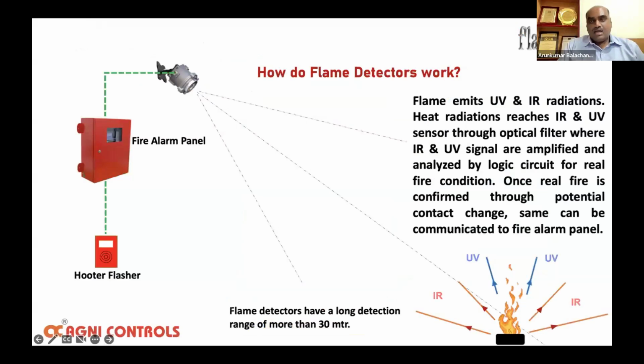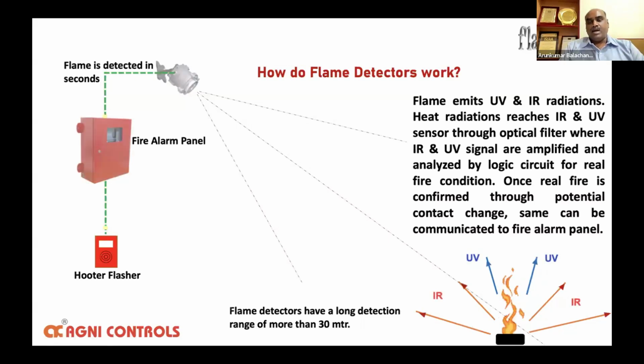So I had compared the flame detectors to our eye. How does the flame detector work? The flame detector picks up the invisible ultraviolet and invisible infrared radiation from a flame. When this radiation falls on the flame detector, it will detect the fire and give the signal to the fire alarm panel. And then activation of a suppression system, or just the alarm, can be programmed through any fire alarm panel.